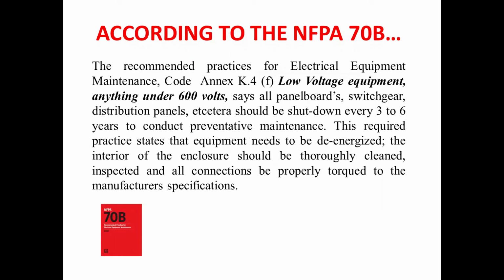According to NFPA 70B, the recommended practices for electrical equipment and maintenance, Code Annex K4F covers low voltage equipment, anything under 600 volts. So if your facility is running 480 or below, 277, whatever it is, it says that all panel boards, switchgear, distribution panels, etc. should be shut down every 3 to 6 years to conduct what is considered preventative maintenance. This is a required practice, and it states that the equipment needs to be de-energized, the interior of the enclosures should be thoroughly cleaned and inspected, and the connections should be properly torqued to the manufacturer's specifications.